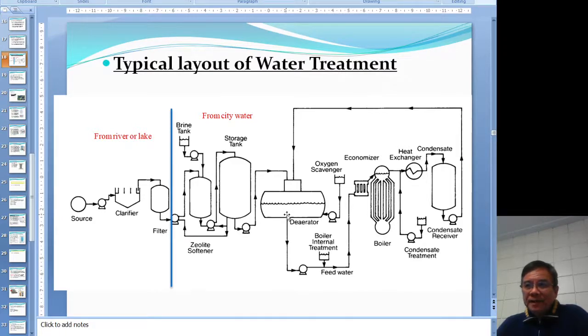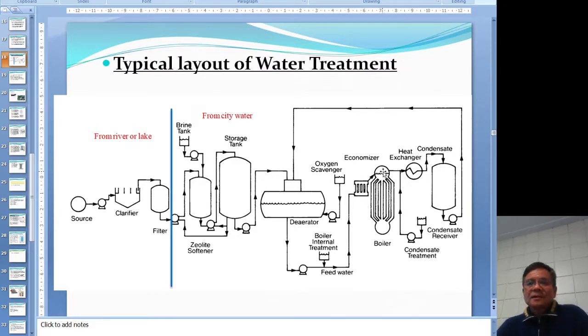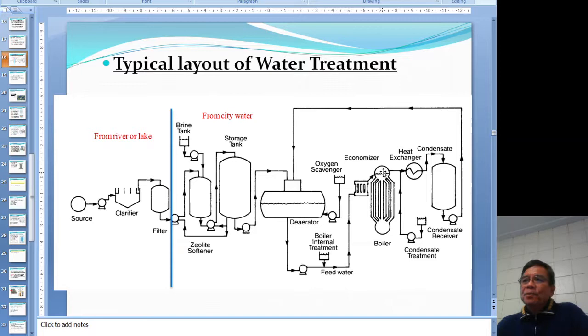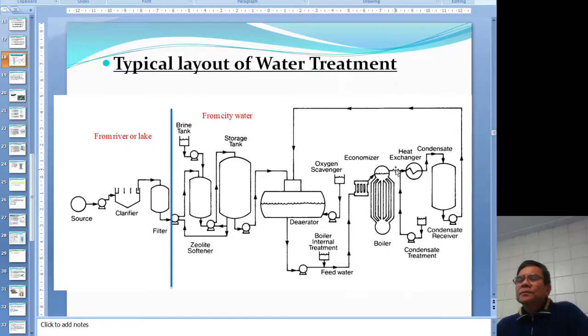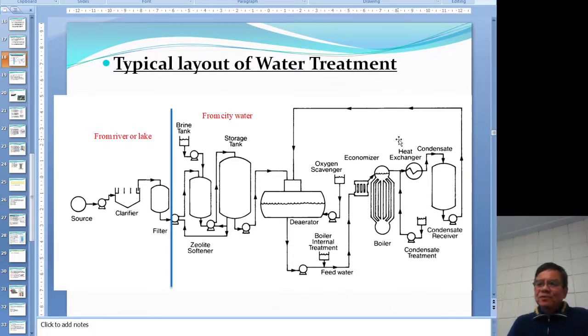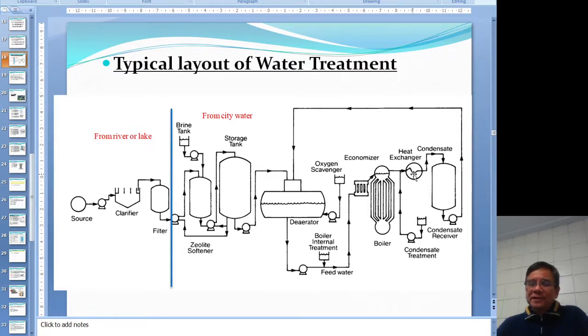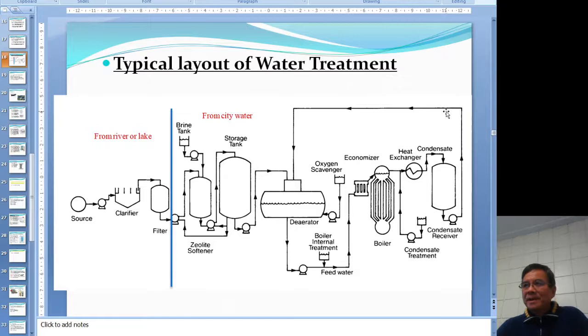You then use a pump to push the water through the economizer side and into the steam drum of the boiler. You produce steam, which goes to the steam user - it could be a chemical processor or a steam turbine. The exhaust from the steam turbine goes into a heat exchanger, which condenses the low pressure steam into condensate. The condensate goes into the storage tank and a pump sends it back to the de-aerator, completing the cycle.